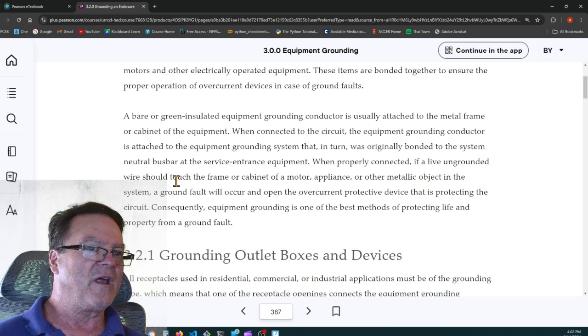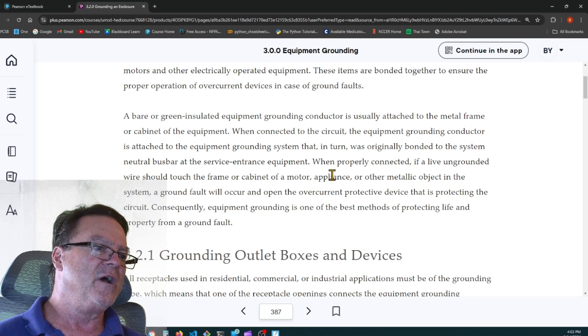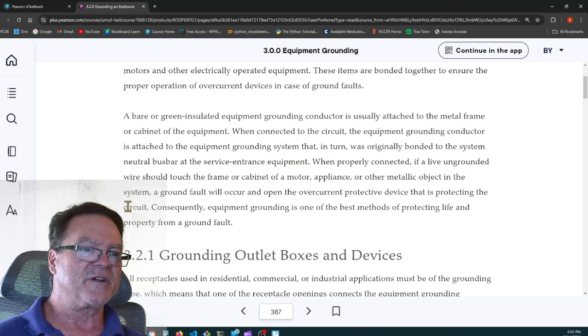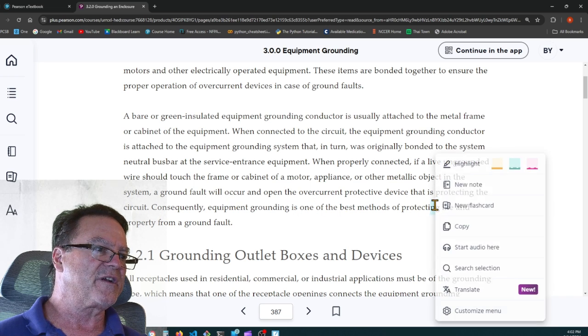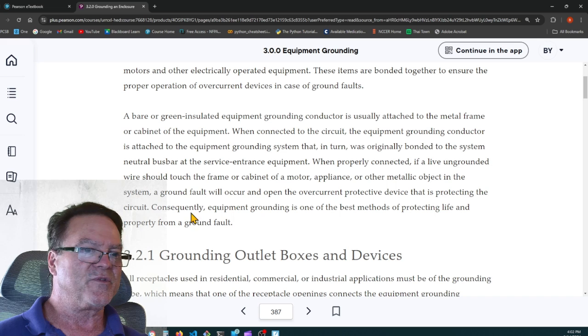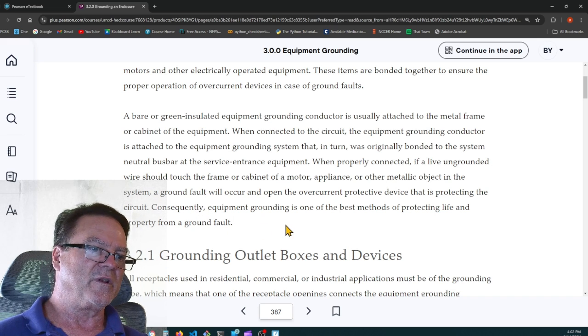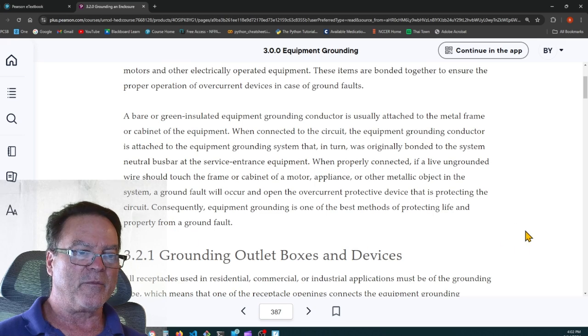When properly connected, if a live ungrounded wire should touch the frame or cabinet of a motor, appliance, or other metallic object in the system, a ground fault will occur and open the overcurrent protective device that is protecting the circuit. Consequently, equipment grounding is one of the best methods of protecting life and property from a ground fault.